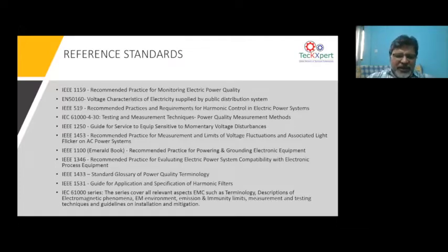The whole process of conversion and inversion is done at a certain carrier frequency. That carrier frequency signal adds up to your fundamental frequency and creates a lot of emissions, both electromagnetic high frequency emissions and harmonic emissions. So 61000 deals with the emission standards and also the immunity standards. If you have a variable frequency drive, an LED, or a computer, there's an emission standard under IEC 61000. Then there is another standard in IEC 61000 itself, which says how much that equipment should be designed to be immune to disturbances. That means emission and immunity are the two aspects covered in the IEC 61000 series standards.